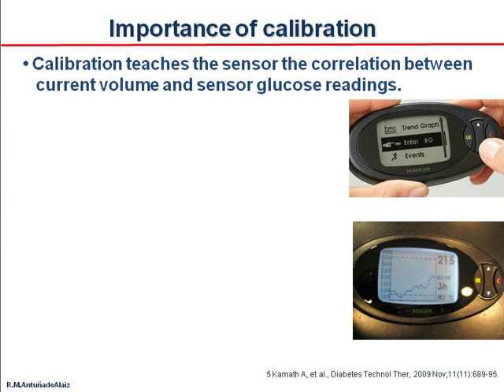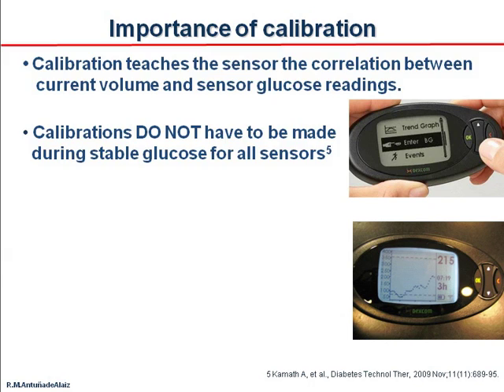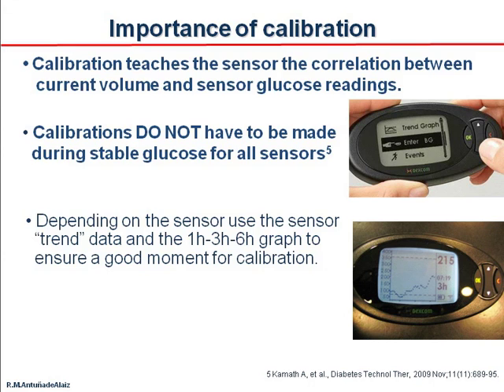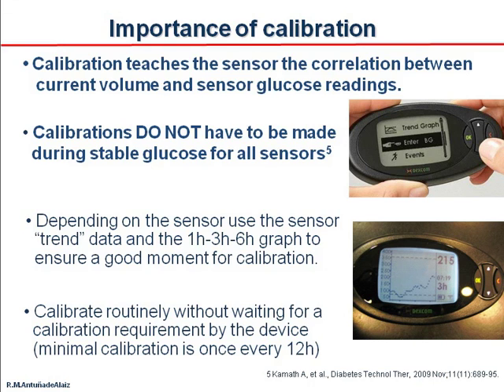Calibration teaches the sensor the correlation between current volume and the sensor glucose readings. And calibration doesn't have to be made during stable glucose for all the sensors. Depending on the sensor, use the sensor trend data of the 1, 3, 6 hour graphs to ensure a good moment for calibration. And calibrate routinely without waiting to be required by the device. The minimal calibration is once every 12 hours, and you can calibrate when the glucose is high, low, or in target.